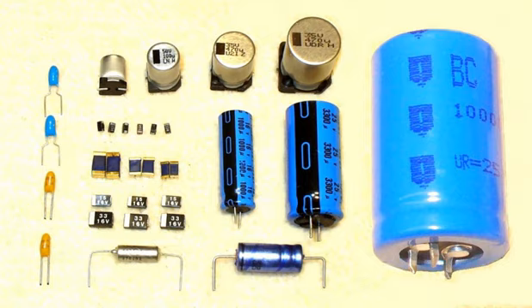This internally generated heat, additional to the ambient temperature and possibly other external heat sources, leads to a capacitor body temperature having a temperature difference of delta T against the ambient. This heat has to be distributed as thermal losses P_th over the capacitor's surface A and the thermal resistance beta to the ambient: P_th equals delta T times A divided by beta. The internally generated heat has to be distributed to the ambient by thermal radiation, convection, and thermal conduction. The temperature of the capacitor, which is the net balance between heat produced and distributed, must not exceed the capacitor's maximum specified temperature. The ripple current is specified as an effective RMS value at 100 or 120 Hz or at 10 kHz at upper category temperature.